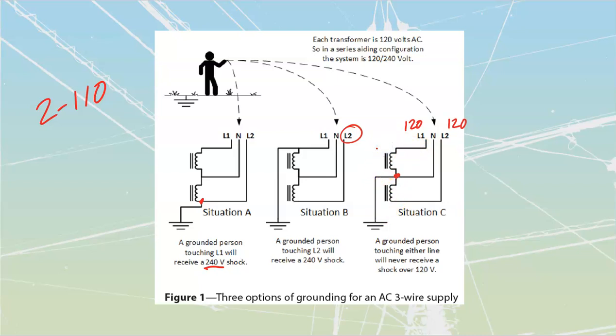It is very rare that somebody will get a 240 volt shock. You'll hear people say, oh yeah, I got a 240 volt shock. Probably they didn't. They might have gotten a shock off of a single leg down a piece of equipment that was connected to 240. But in order to get a 240 volt shock, you would have to have somebody that would be isolated from ground. So we will float this dude. We'll place him on a little rubber mat there, so he's isolated from ground. And the dude himself would have to touch line 2 with one arm and hold on to that, and then with the other arm touch line 1, and the rest of the body would have to be isolated from ground. At that point, they could actually get 240.